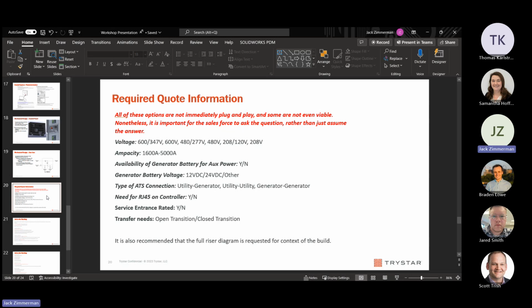Not offhand. I mean, the biggest things I would have questions for is when they're trying to fit stuff - we say the ampacity is up to 5,000 amps, but if we actually do 5,000 amps, you're not going to fit it in the same form factor we use on these previous ones in a deluxe pad mount, and have to go to like a triple pad, which then you're doing some different stuff with bus bar. But the controls and everything that was described on how that system would work would still, I think, be the same, so I don't really have any other questions.